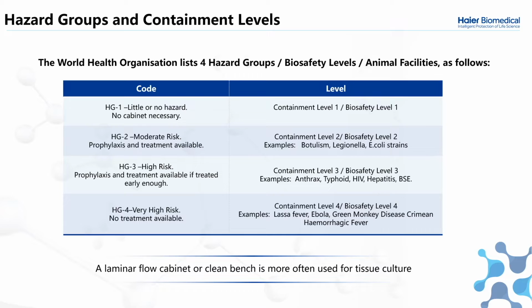Hazard group 3 represents high risk samples, and these are things such as anthrax, typhoid, HIV, hepatitis, and BSE. Containment level 3 or biosafety level 3 is when a class 2 cabinet is definitely required, and the customer will also be able to advise you on what they're working with and if it's appropriate. Once you reach hazard group 4, you exceed what the class 2 biological safety cabinet can handle, and in these cases there's more specialized equipment to be used. These are things such as Lassa fever, Ebola, green monkey disease, and Crimean-Congo hemorrhagic fever.